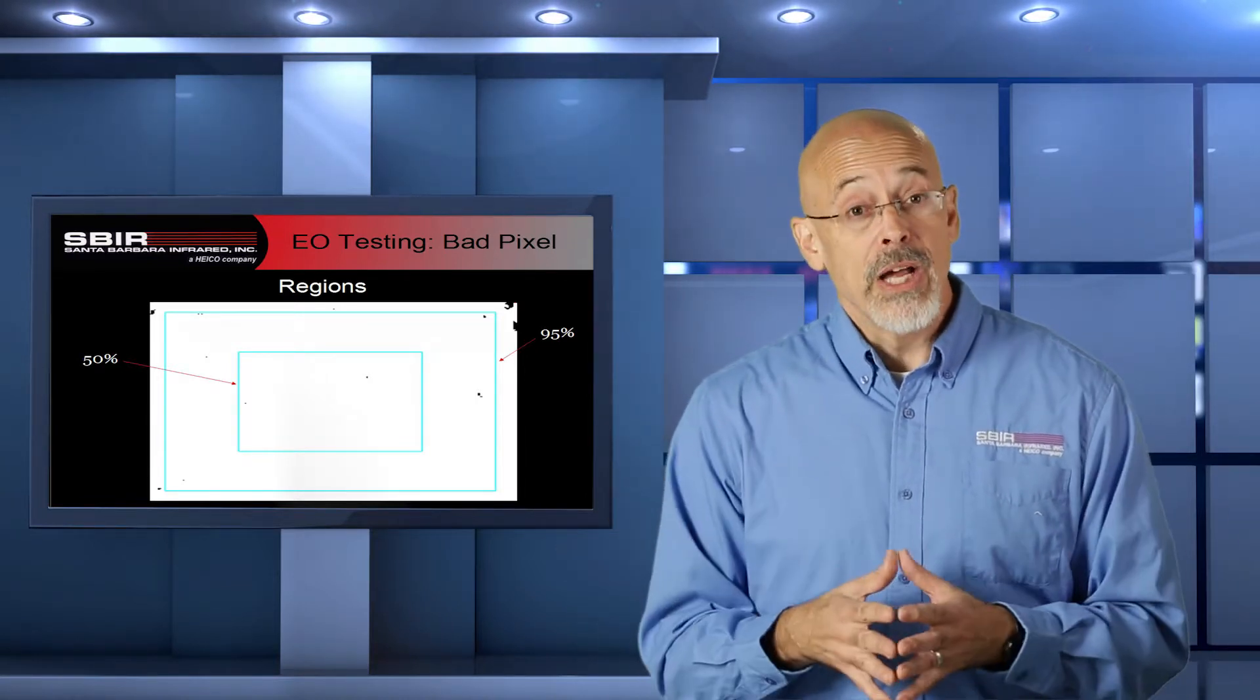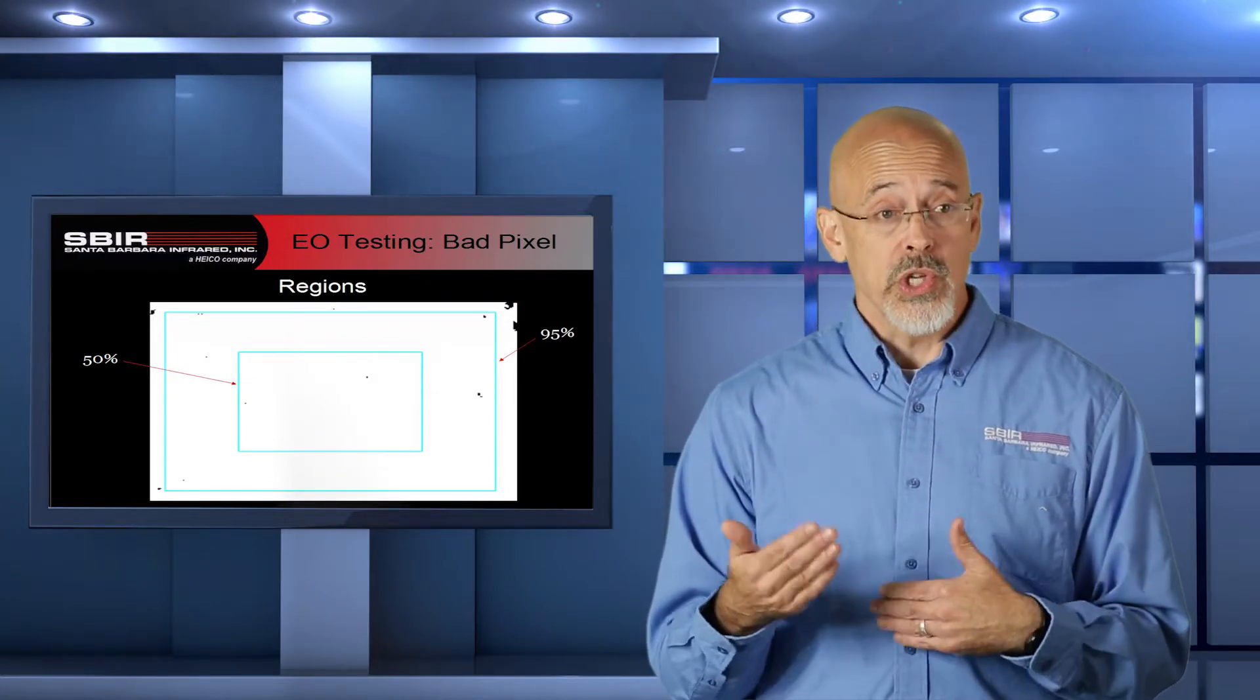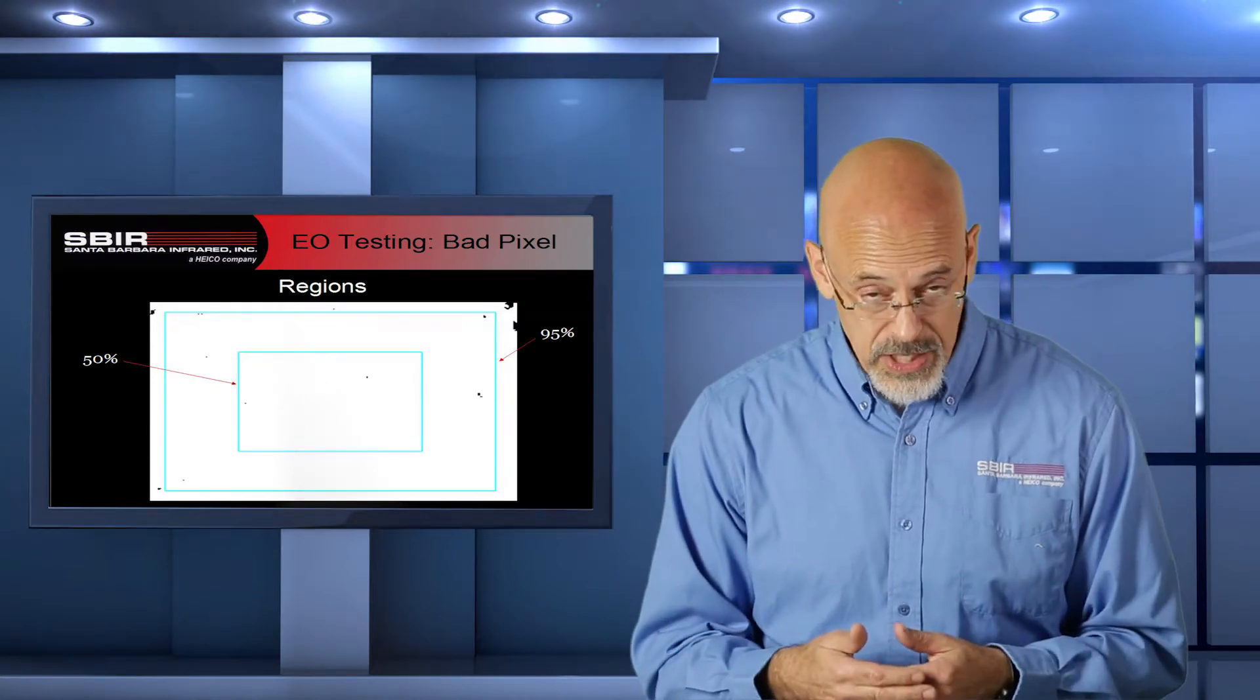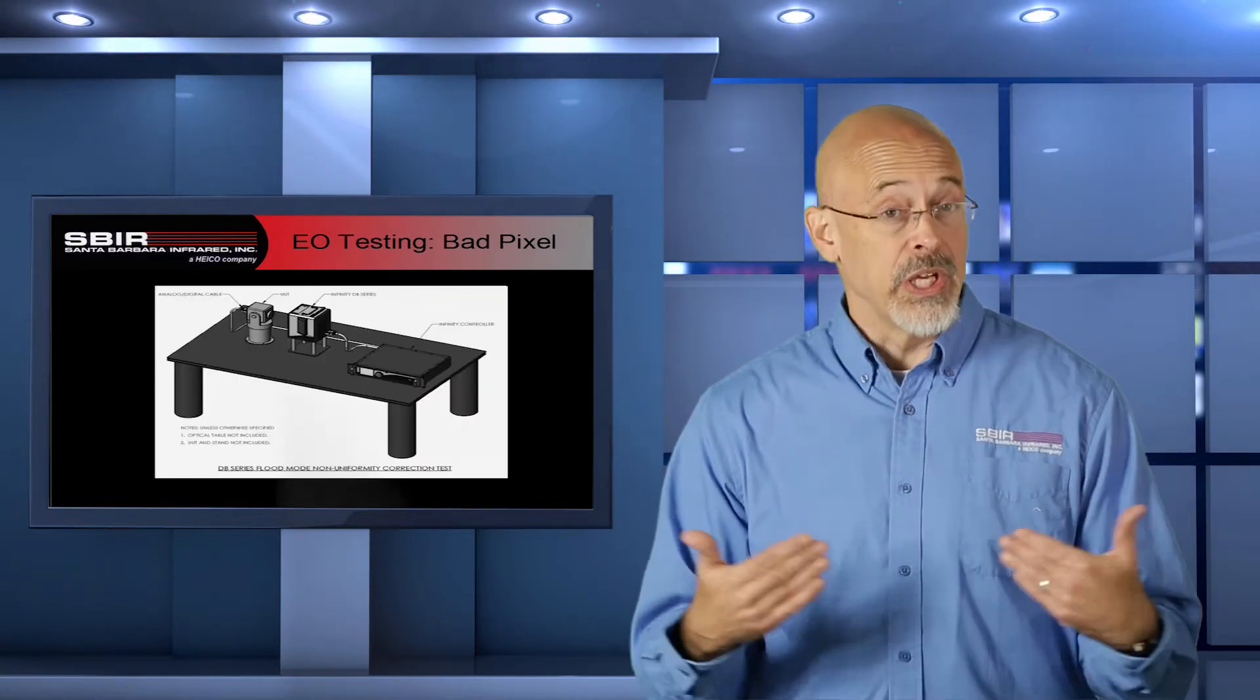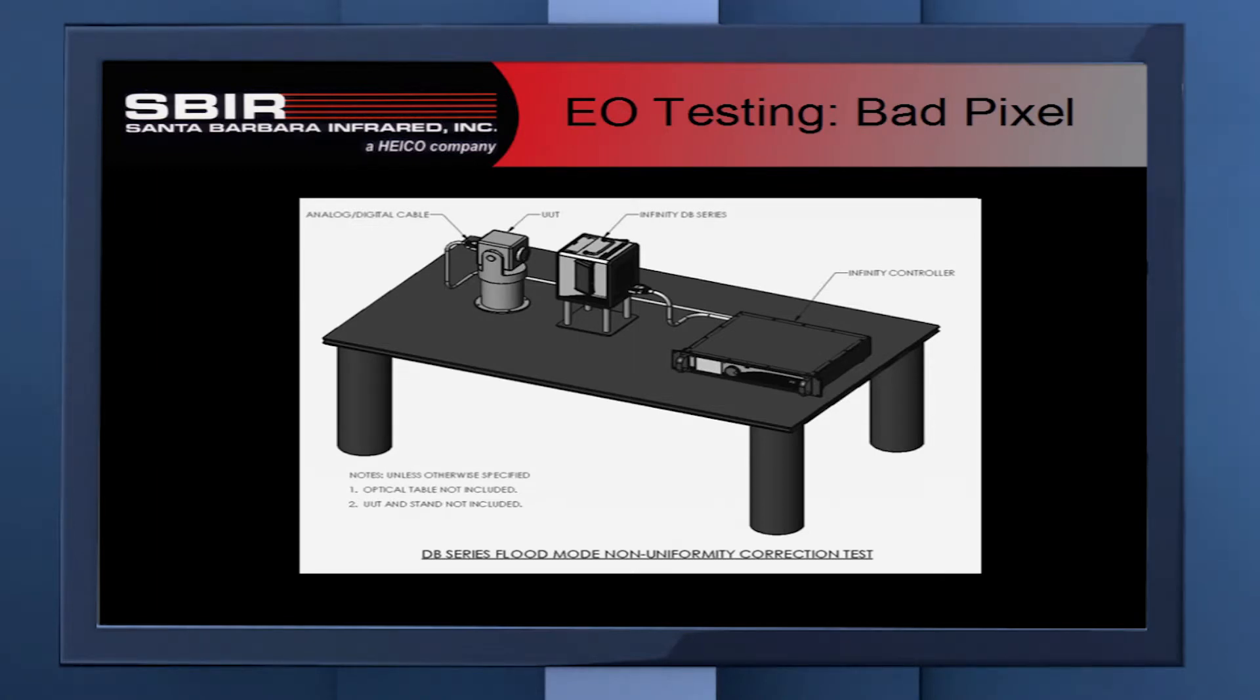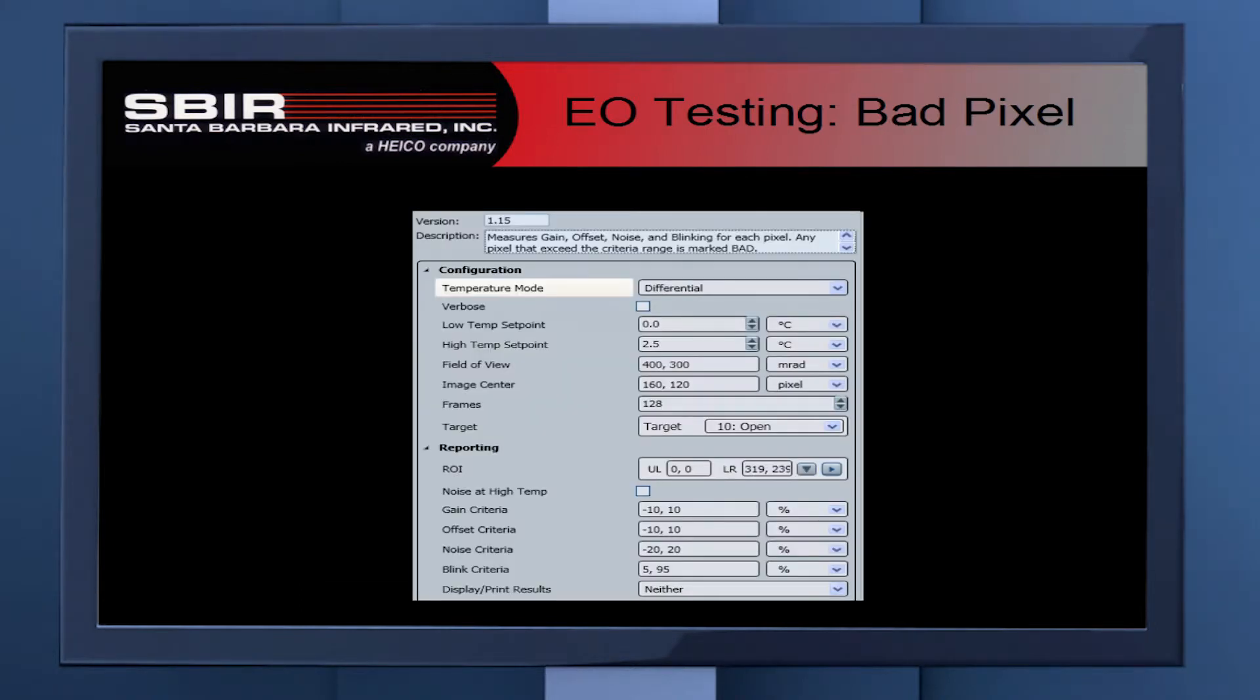So, how do we go about doing this test? In this case, we actually need a calibrated source, because we're going to be measuring the gain on these pixels. It's similar to what we're doing with SITF. So we use a calibrated blackbody, and we are going to present that blackbody's radiation at two different temperatures. We can do this either in a flood fashion, where we put the blackbody right up against the camera, or we can do it in a projected system where we project out that image in a known area, so we know what part of the camera we're illuminating at any given time.